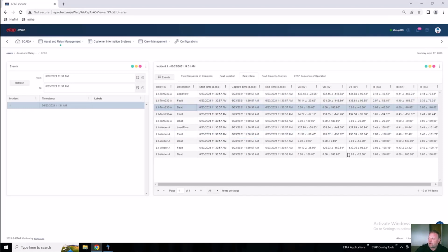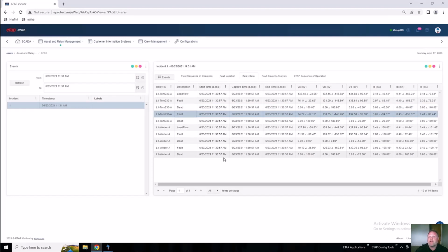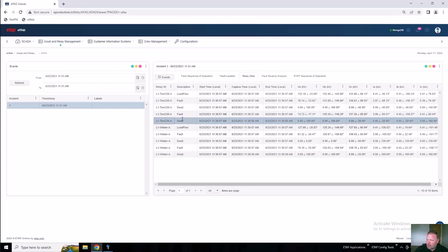Now, then the line goes dead. This is the relay protection coming in and tripping off the relay. And then we see another fault. That's because we reclose. We close up the circuit breakers just to see if maybe the fault has been isolated or if it was a temporary fault. And here we can see, because the next step is dead, that again, this is a permanent fault, and that the entire line is being de-energized.